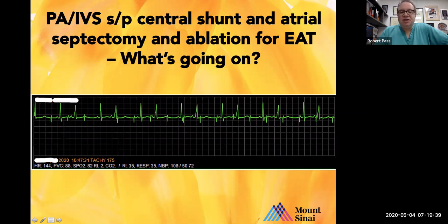And actually, Grace increased the output on the device quickly, ran upstairs, and was able to pace 1-to-1 at 100 beats per minute. So now the next question is, so that was obviously bad, and we're going to need to do a little bit of education for the nurse who just sort of blindly plugged this in. And had I not, what's the downside of this?